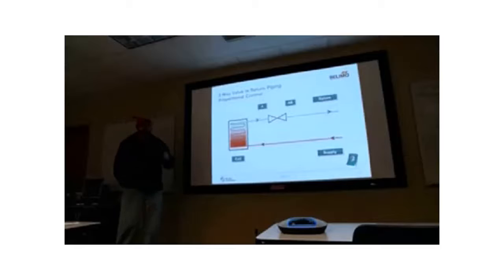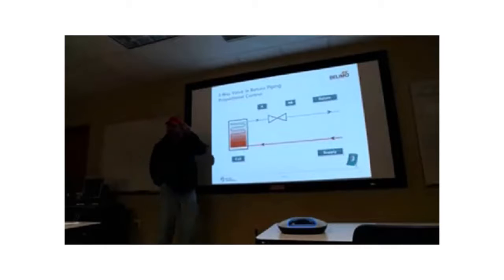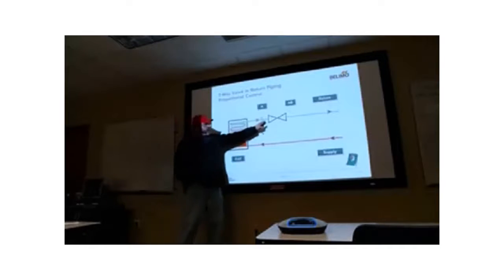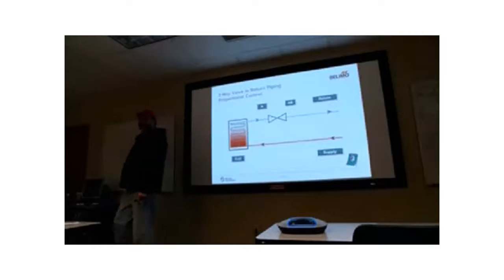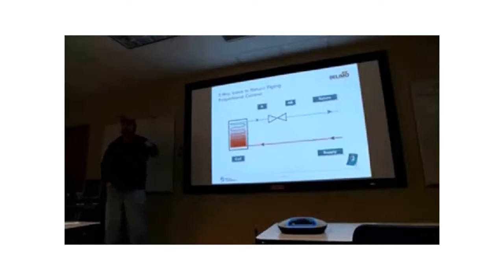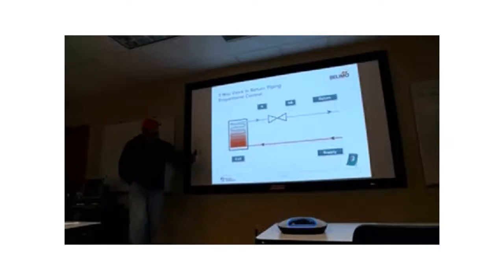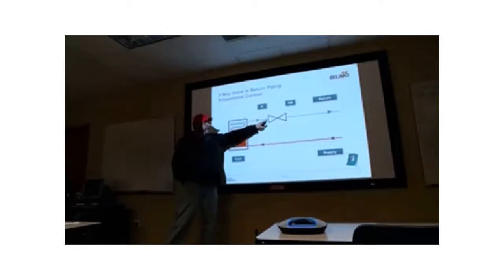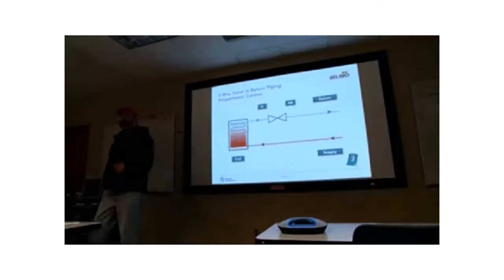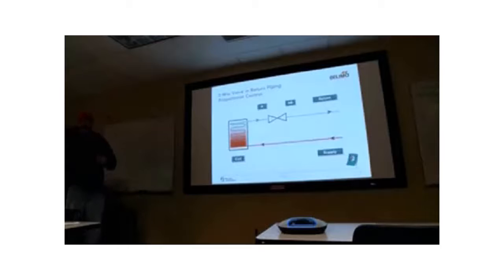You're modulating, and that's where that characterizing disc is. Remember, for characterizing the equal percentage characterization? The disc is actually in the A port. So that's where you characterize the flow like that funny looking curve I saw. That's where it is. On a ball valve, that's where that characterizing disc is. It's in the A port, and it's characterizing flow. On a three-way valve, it's also in the A port. And that'll make a little bit more sense, hopefully.